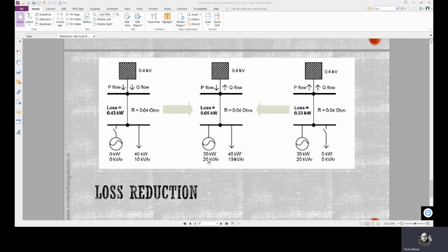Now, what about Q flow? 20 kVAR is generated locally, but 10 kVAR is the local reactive power demand. So we have excess reactive power at the local node side. So the Q flow has also reversed. It is towards the upstream grid now.